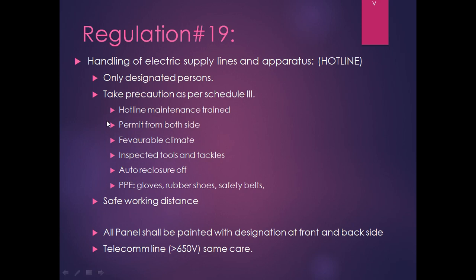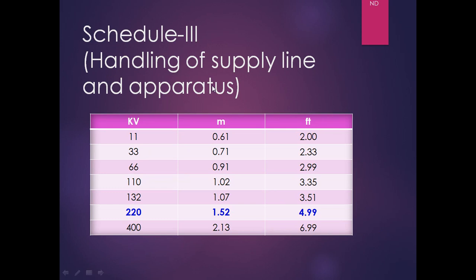Now we'll discuss the clearance, but just keep in mind that this clearance is specified for the specially trained persons, or we can say the hotline trained persons. This is not for everybody. So what is the recommended distance? This is mentioned in the schedule 3 of the regulation 2010. For every nominal voltage level, they have mentioned a safe working clearance. For 220 kV, the minimum working clearance should be 1.52 meter. For 400 kV, it should be 2.13 meter.